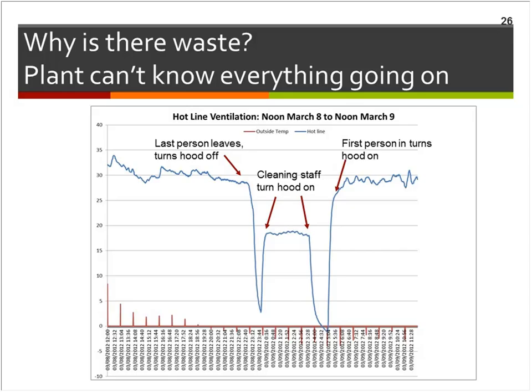The facility was convinced that during the night, that fume hood is off. But if you look at the blue line, you see the line goes down once everything's turned off, but very shortly thereafter it comes back on and stays on for most of the night. What was actually happening is that when the cleaning staff came on, they just turned everything on in the area, including the fume hood. There's so much that goes on that people aren't aware of on the plant, because you can't possibly know everything.